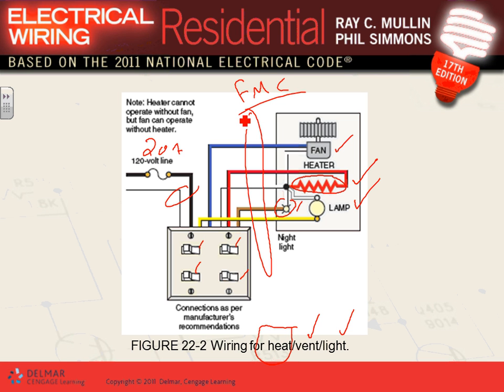Typically, we wire with an NM cable, right? There's a way of pulling 2 neutrals. You can take these two with 1 neutral, these 2 with 1 neutral, and pull it with 2 cables. But the proper way of doing it is 1 flexible metallic conduit from the box here into where the fixture is located, and pull the 5 wires. 1, 2, 3, 4, 5 wires. Any comments, guys, about this special type of fixture?